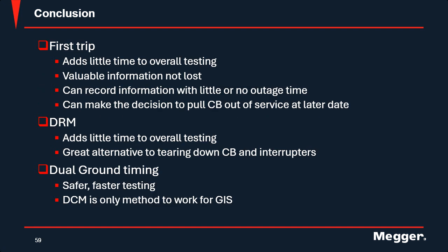So we talked about First trip, DRM, and dual grounding. Post-trip just adds a little more time to overall testing, but it is valuable information that's not lost. It can record information with little or no outage time because everything's done inside that control cabinet. If you're still in service and you don't want to pull it out, you can base it all off your first trip test. If that first trip test comes back good, you can push out the maintenance service for that circuit breaker to a later date.